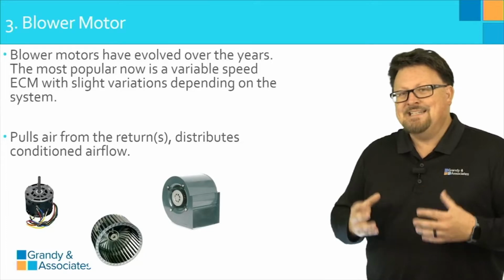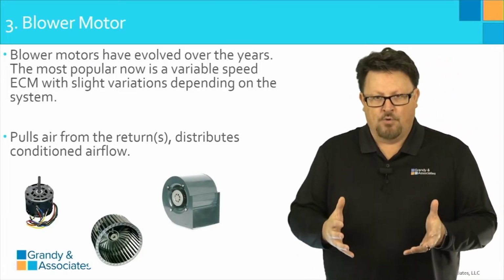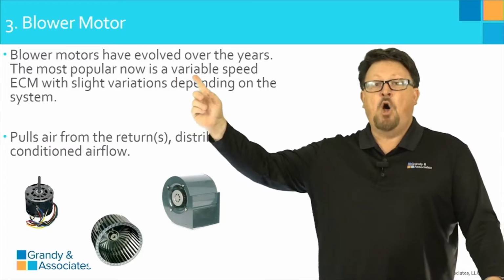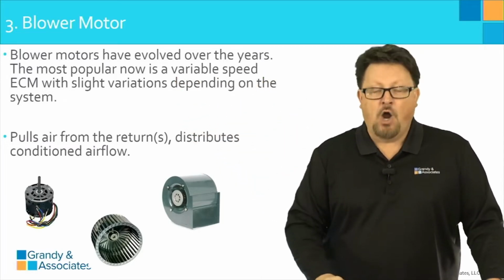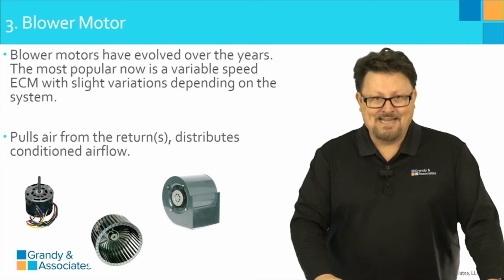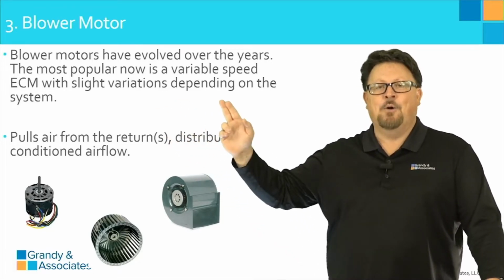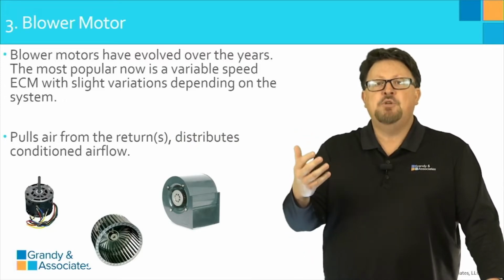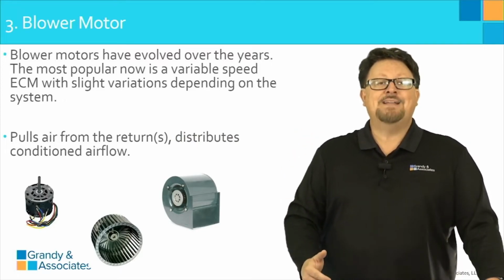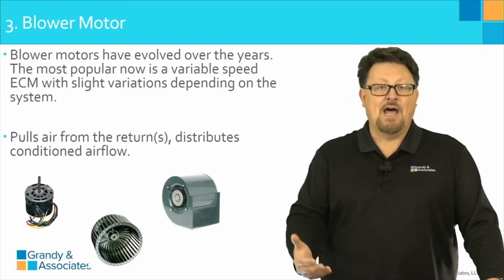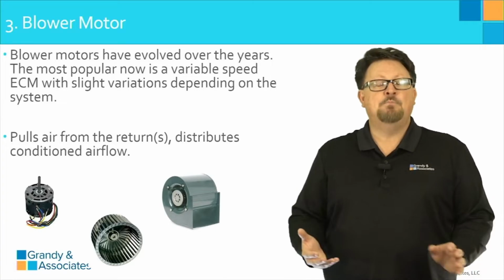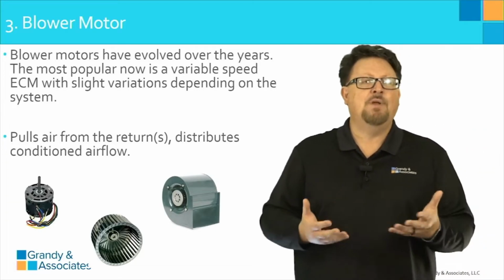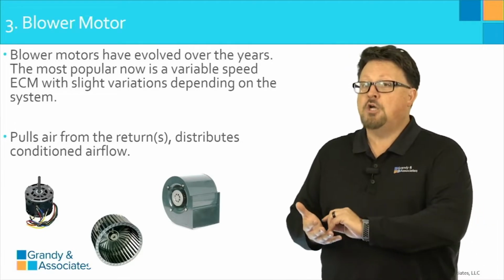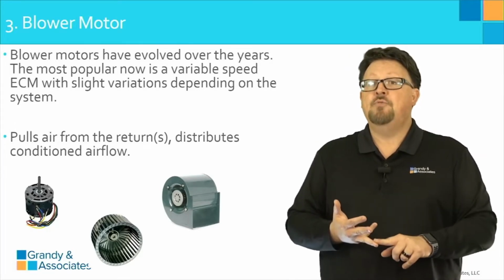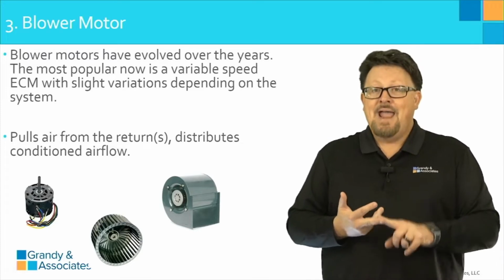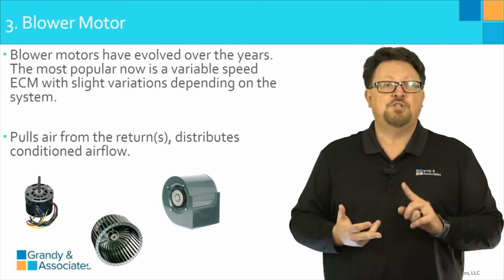The blower motor. Inside the air handler, there is a blower motor. Now, I will tell you that blower motors have evolved over the years. The absolute darling of the HVAC industry today is something called an ECM blower motor, electronically commutated motor, or you may hear it referred to as an electronically controlled motor. The ECM blower motors have become the darling of the industry for really a few reasons. One, they work across a wide range of equipment options. Two, they're very efficient to operate, and they tend to be the quietest of the motor options available.